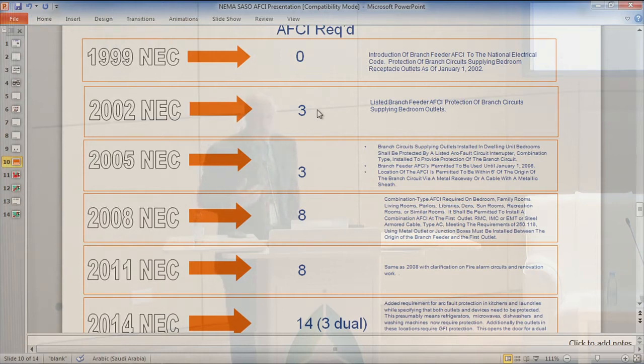There were areas where people were asleep and could easily be overcome by the smoke before they knew what was going on, or perhaps a smoke detector would go off. So starting with that, we went through it in 2005, 2008, 2011, and now with the 2014 code, it's roughly 14 circuit breakers per home. It's only on 120 volt, or what would be your 220-volt circuits, single pole circuits.